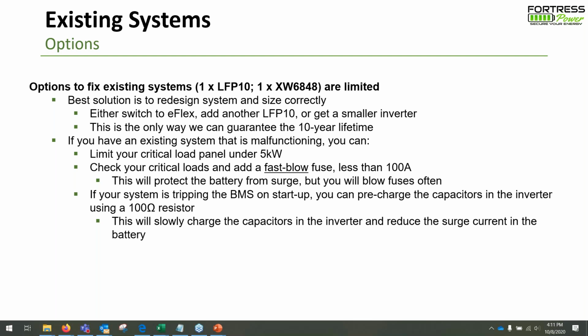The reason is, if we have an inverter that is capable of pushing continuous current more than what the battery is capable of, we cannot guarantee the lifetime. No matter how small the loads are, we cannot guarantee the lifetime. If you have an existing system that is malfunctioning, you can limit your critical load panel under 5 kilowatts. Under 5 kilowatts means under 100 amps at 50 volts. So if your critical load panel is under 5 kilowatts, it'll be much easier on the battery.